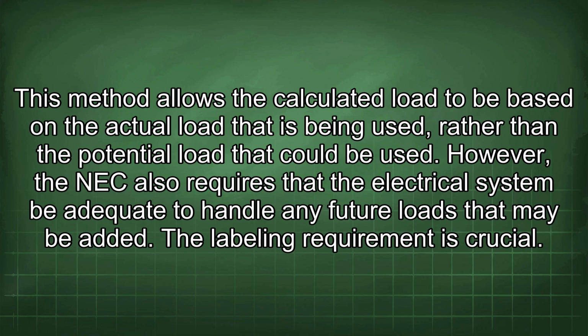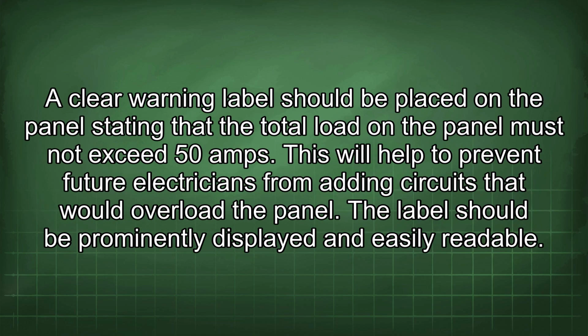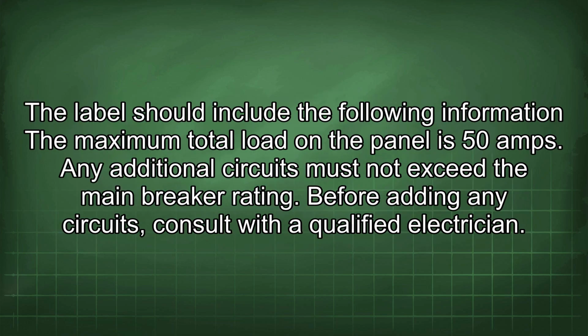The labeling requirement is crucial. A clear warning label should be placed on the panel stating that the total load in the panel must not exceed 50 amps. This will help to prevent future electricians from adding circuits that would overload the panel. The label should be prominently displayed and easily readable. The label should include the following information: the maximum total load on the panel is 50 amps. Any additional circuits must not exceed the main breaker rating. Before adding any circuits, consult with a qualified electrician.